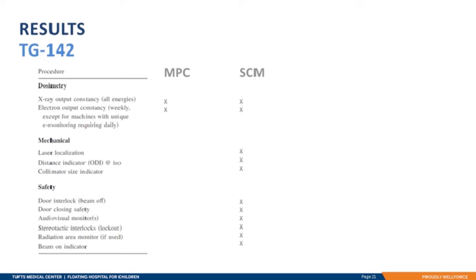Next up, we looked at TG-142 test satisfaction per platform. Machine Performance Check does report on beam output constancy, but since it is not designed as a platform for daily QA, it does not collect data on any of the mechanical or safety tests, and while some of these checks could be assessed while MPC is being performed, there isn't any way to record results of these tests on the Machine Performance Check platform. SunCHECK Machine, however, does. The dosimetry tests are automated with the daily QA3, while the rest of the test results can be manually entered into the system.